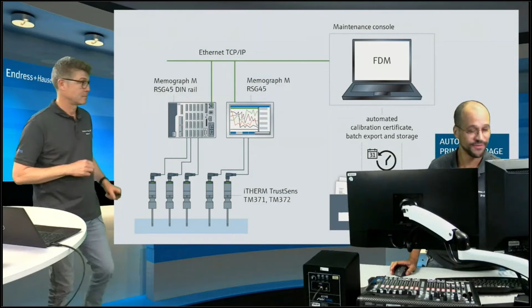So how can the certificate be downloaded without the data manager or the FDM, so all those different bypasses? Yeah, it's also possible. This is a HART protocol instrument. And if you have a HART-capable engineering tool like Endress+Hauser DeviceCare or FieldCare, you can connect yourself to the sensor directly and download the certificates using this DTM, device type manager driver, and you can generate PDFs, you can adjust, you can look at all of the data which is inside. This is another possibility to work with this. So basically how most of you use the HART communication either way, to parameterize, to do the changes, etc.